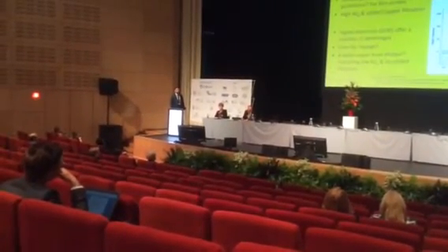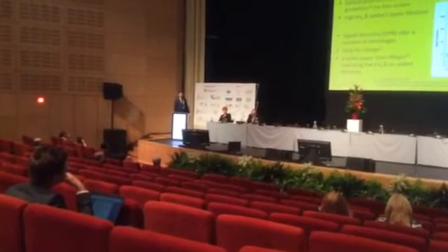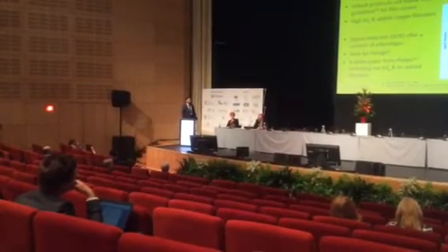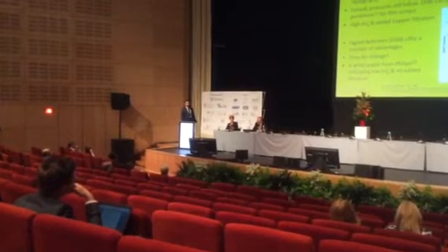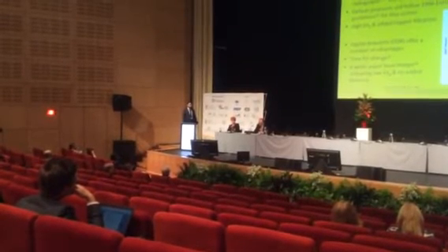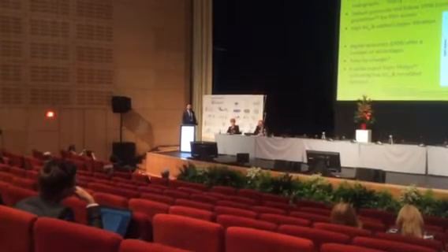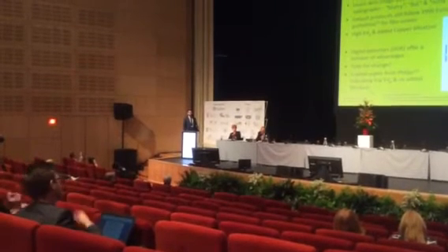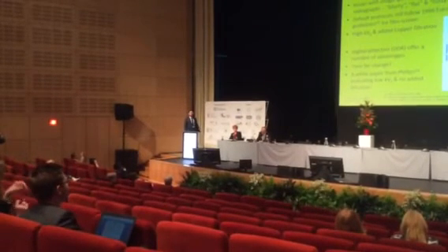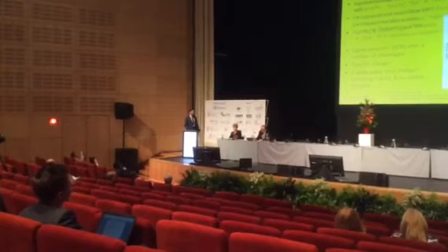So after completing a literature review, I found one relevant paper in terms of digital imaging of paediatric extremities, and this was some work by Philips. It's a white paper, and they used a small block of PMMA and a thin strip of aluminium to simulate a paediatric extremity. And the results of this suggested that actually you could remove this copper and lower the kV and get better image quality.